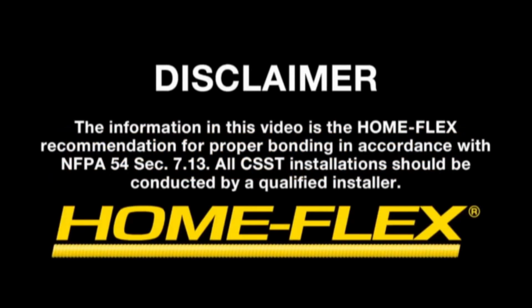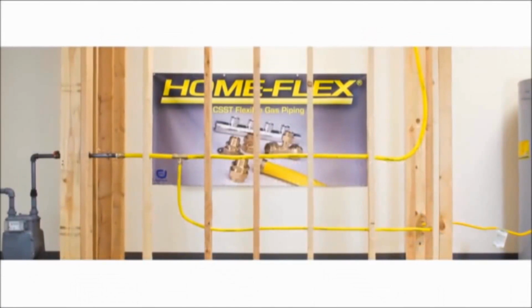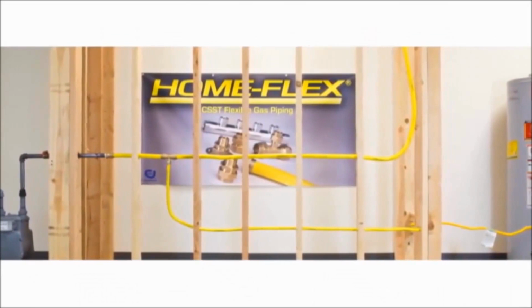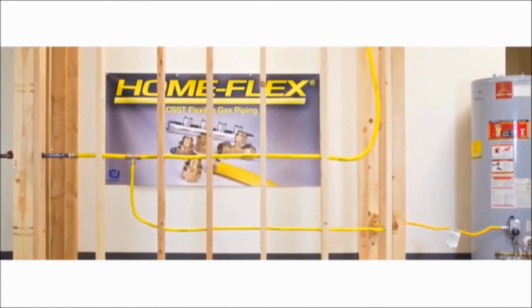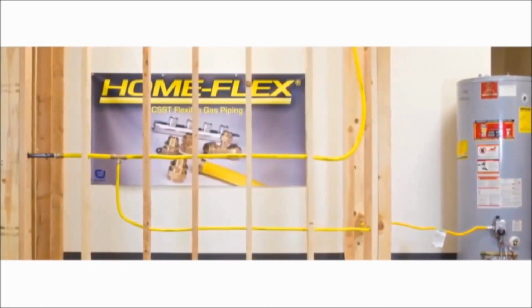Disclaimer: the information in this video is the HomeFlex recommendation for proper bonding in accordance with NFPA 54 Section 7.13. All CSST installations should be conducted by a qualified installer. When installing corrugated stainless steel tubing, or CSST, just like black iron pipe, you must bond the system in accordance with NFPA 54 Section 7.13.